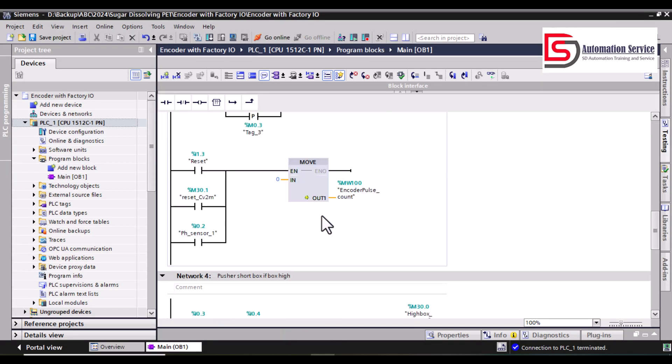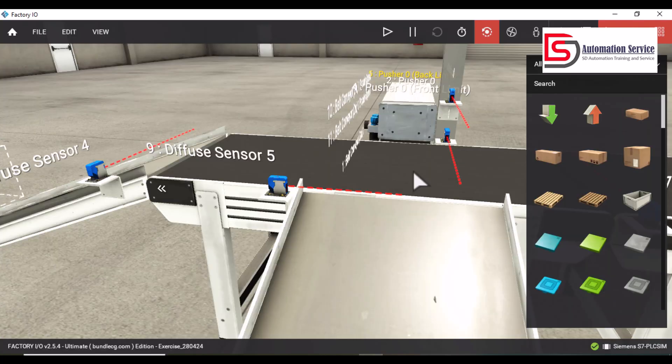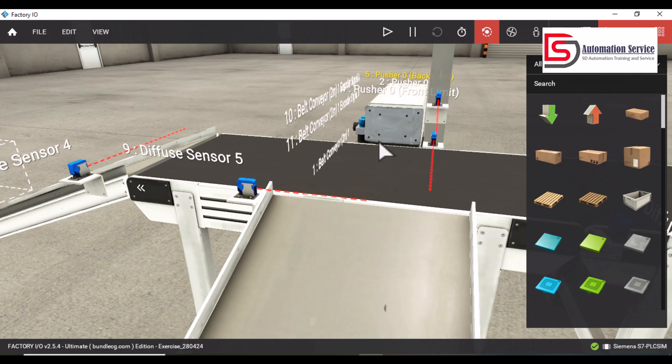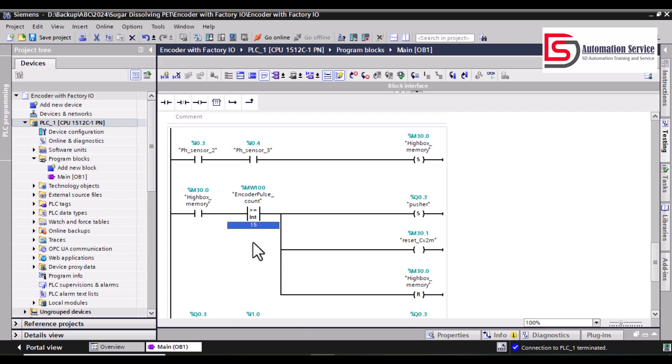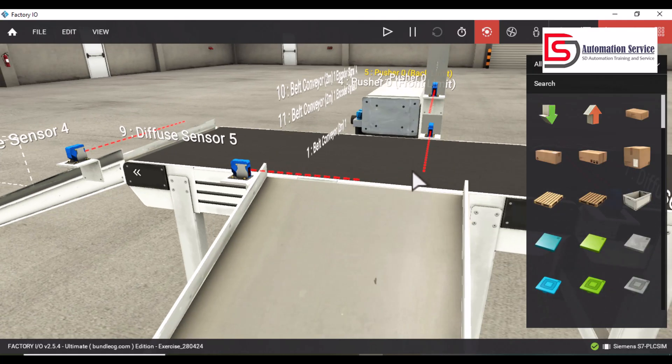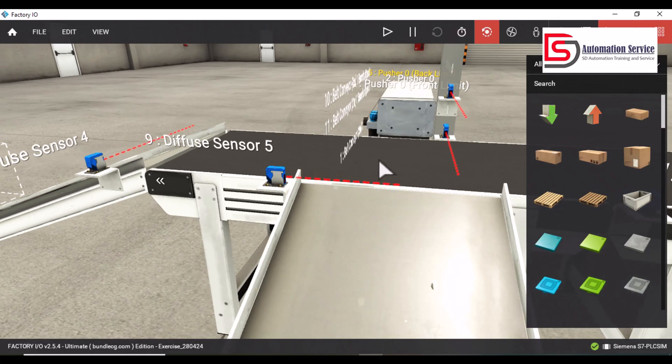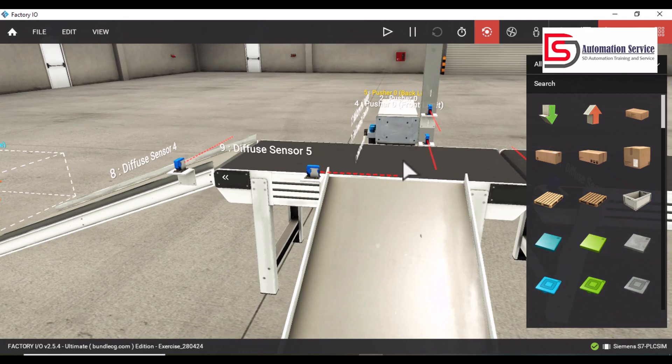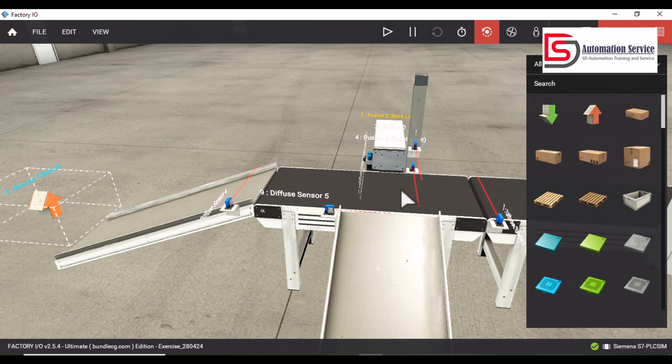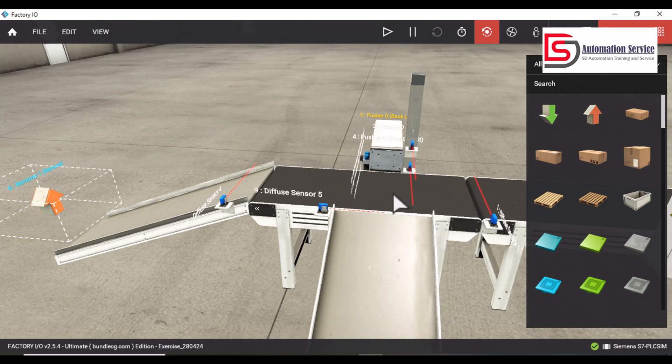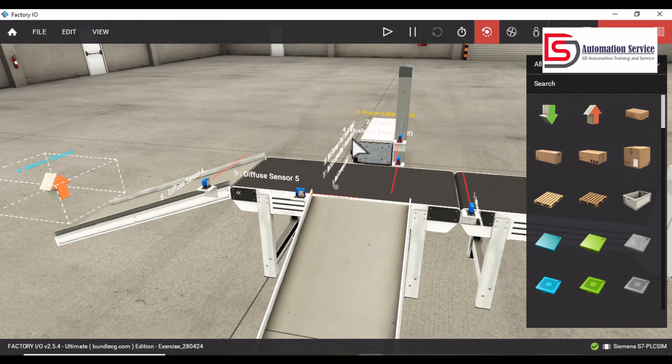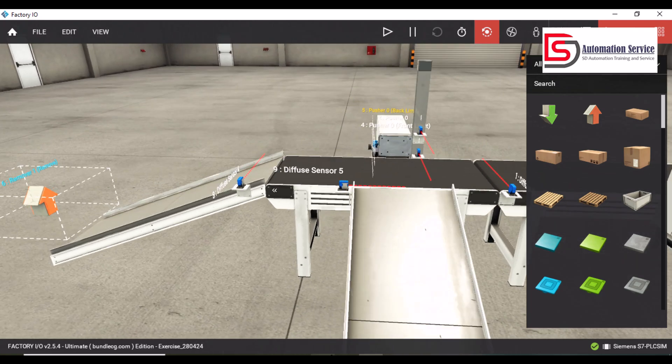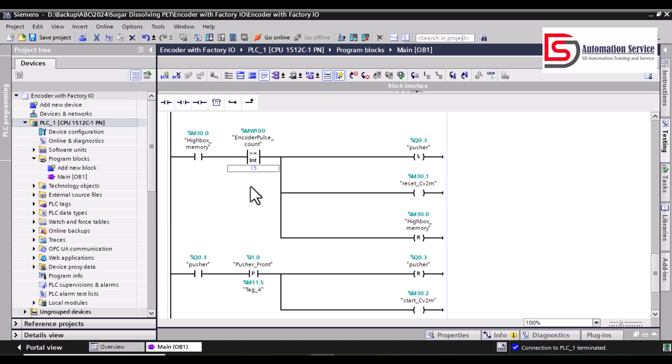I use that value for my project. The value when the box comes in front of the cylinder is around 15, so I use 15. You can put this by manual testing and you can see the value from the encoder and how much that box delivers to your position that you want to reject or when you want the conveyor to stop. You can test it manually one by one. Once you get the data value, we can put this value to make the system automatically.